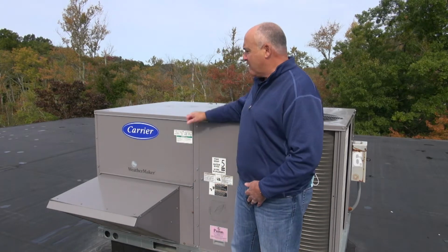As you can see in the background, we've got a Carrier 5-ton rooftop, and over to the right of me that you can't see right now, we've got an older Lennox unit from probably about 2008. What we're going to be doing today is performing HVAC maintenance on the equipment, and we're going to go through our checklist to show you the value and the importance of doing HVAC maintenance on your rooftop units.